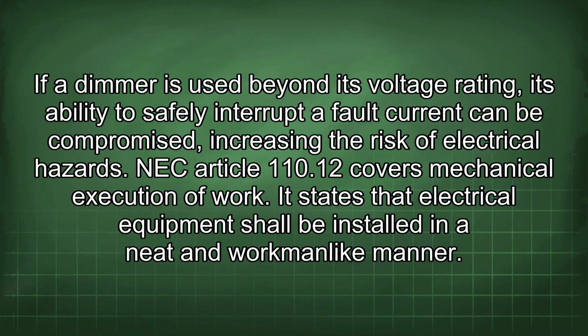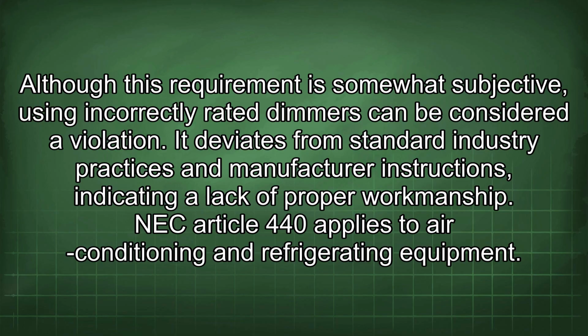NEC Article 110.12 covers mechanical execution of work. It states that electrical equipment shall be installed in a neat and workmanlike manner. Although this requirement is somewhat subjective, using incorrectly rated dimmers can be considered a violation. It deviates from standard industry practices and manufacturer instructions, indicating a lack of proper workmanship.